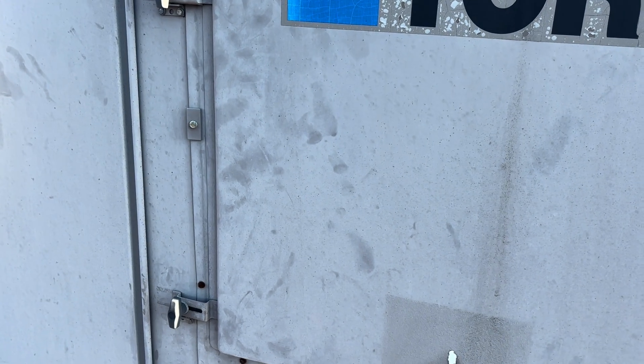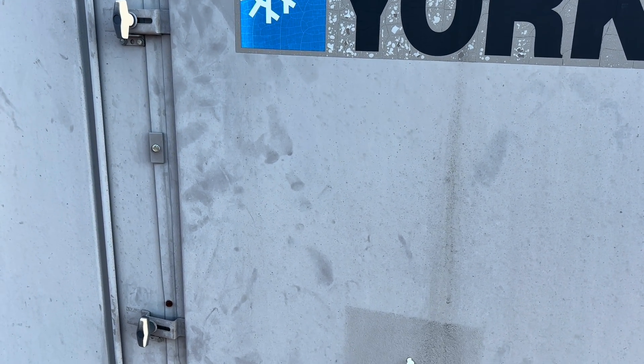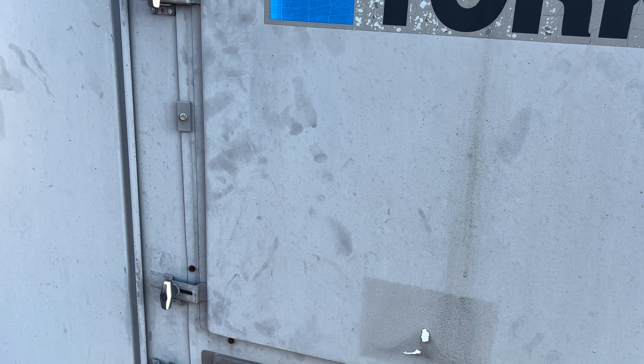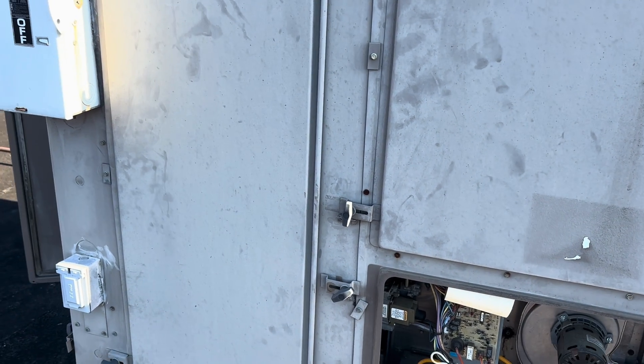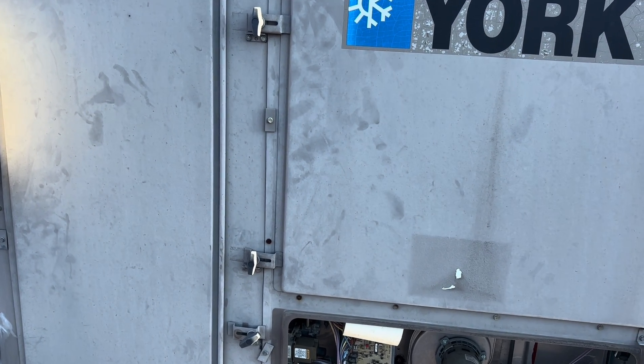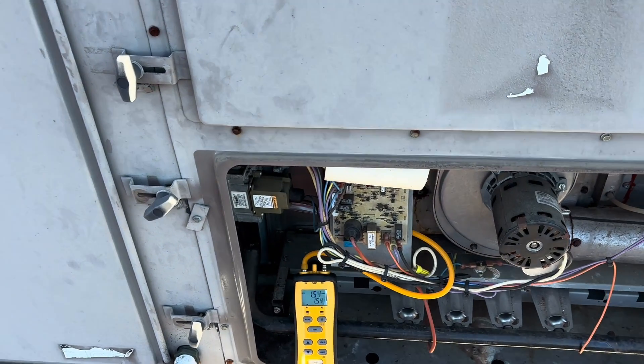It's just weird that that happened after a power outage — or a power surge, or whatever happened here. Let's try to figure this out: if it was mid-cycle and the unit stopped abruptly, if everything stopped without cooling itself down, that could happen — but that would be like just turning the disconnect off. The only scenario is if the unit stopped abruptly without the extended fan runtime cooling the heat exchanger down.